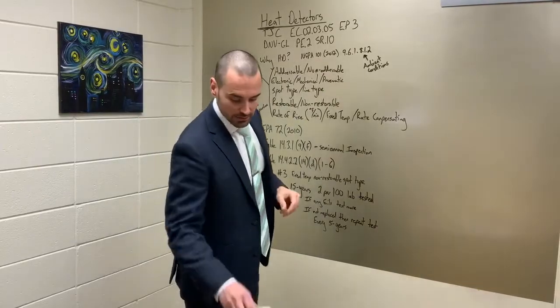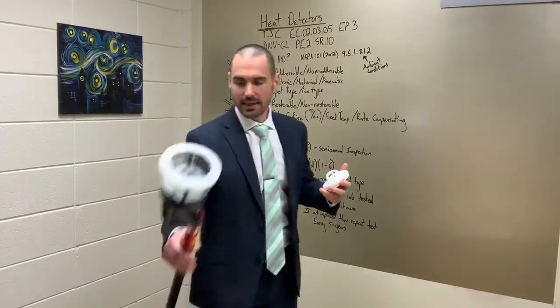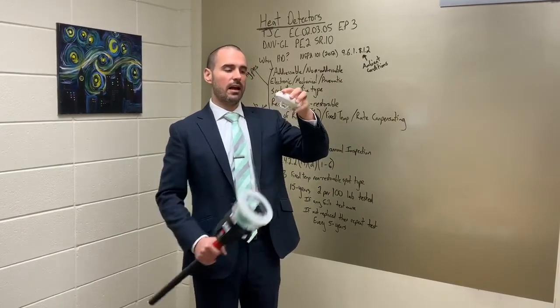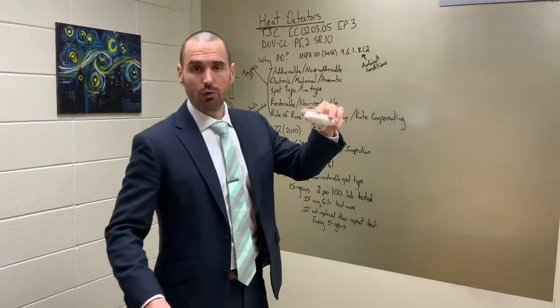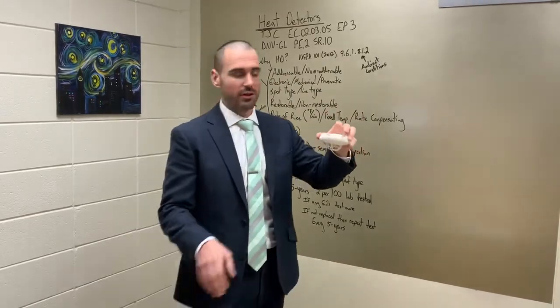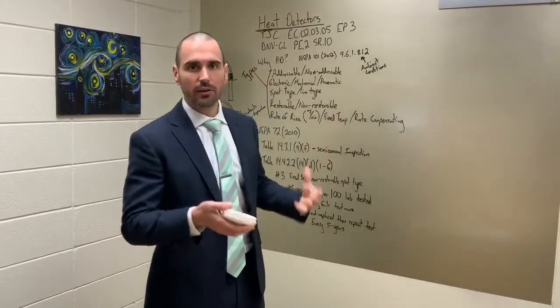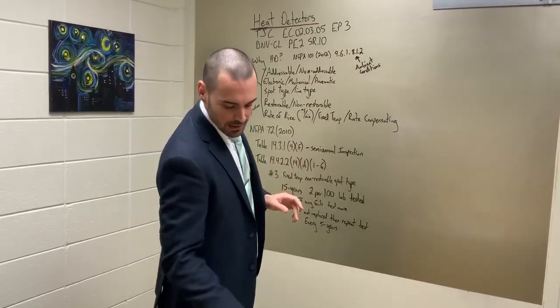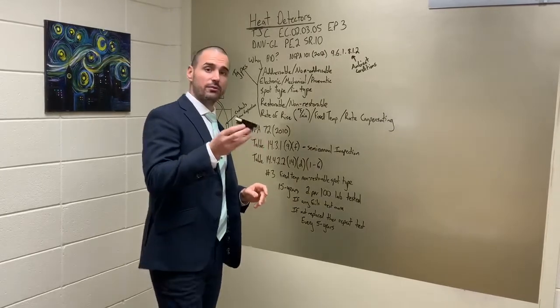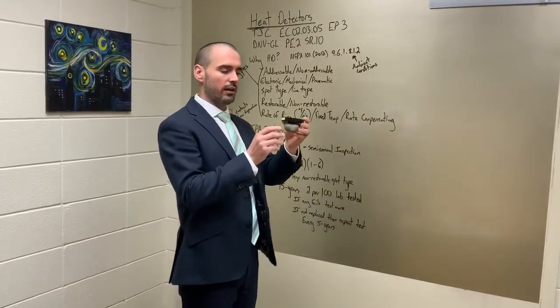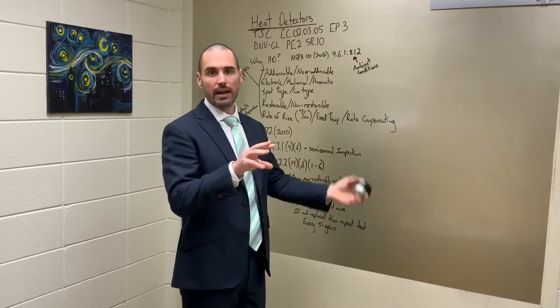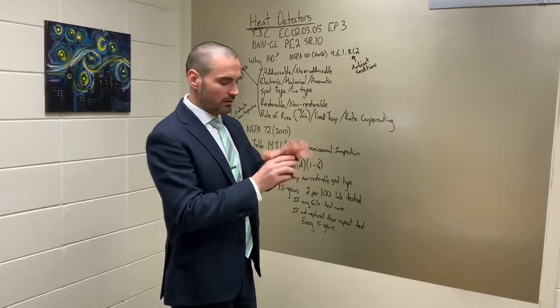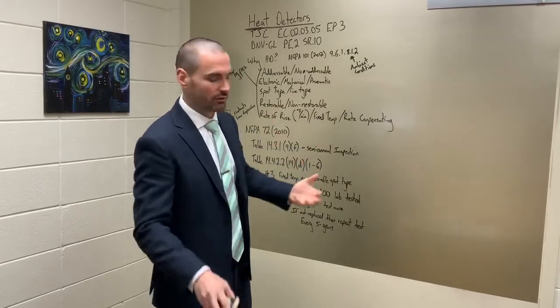Restorable and non-restorable. A restorable detector simply means that when you test that detector or when that detector goes into an alarm, once it goes into an alarm and that heat is removed, it will reset back to its normal condition. You still have to reset the panel to get rid of the alarm condition, but the detector itself is resettable. Non-restorable is where it's a one-time use. When it goes off, you throw it away and you replace it, much like a sprinkler head.